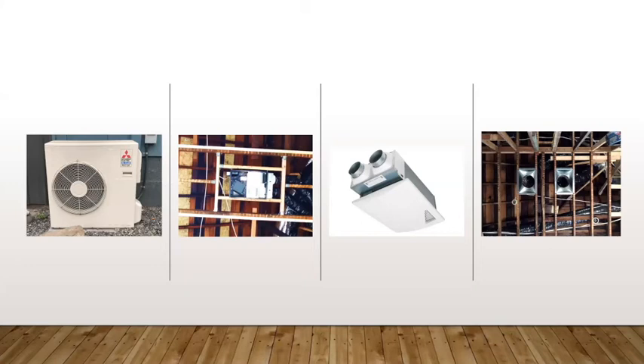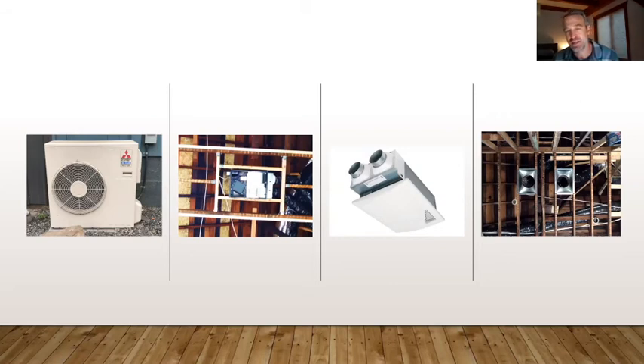Yeah, so this one kind of looks like a large exhaust fan like you'd have in a bathroom. And it just runs continuously in the background at a really low rate of about 10 CFM. A bath fan runs at about 100 CFM, so it's about 10% of the air movement. So it doesn't need that much electricity to run.